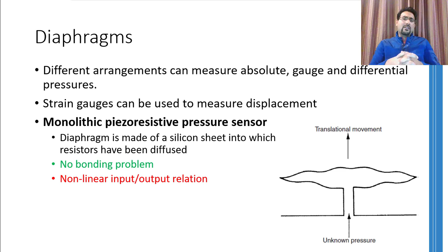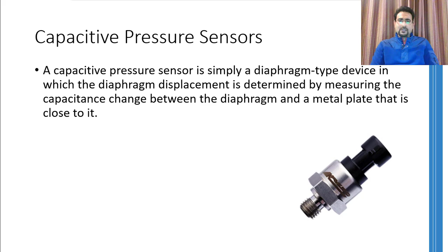Capacitive pressure sensors employ this diaphragm, where the diaphragm acts as one plate of the capacitor, and as it expands, the distance between the two metal plates of the capacitor decreases. Measuring this change in capacitance can give you the value of the pressure. As measuring pressure through a diaphragm is just the case of measuring displacement of the diaphragm, any displacement sensor can be used over here. The arrangement in which fiber optics can measure the proximity of a reflecting surface can be used to measure the displacement of the diaphragm.